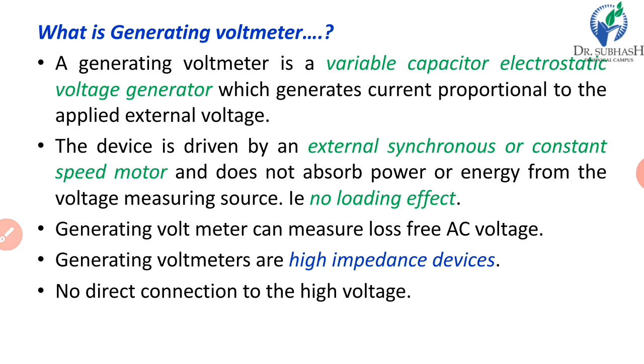Now we will start with the generating voltmeter. What is a generating voltmeter? A generating voltmeter is a variable capacitor electrostatic voltage generator which generates a current proportional to the applied external voltage. The device is driven by an external synchronous or constant speed motor and does not absorb power or energy from the voltage measuring source. It means there is no loading effect. We can say it is an advantage also.